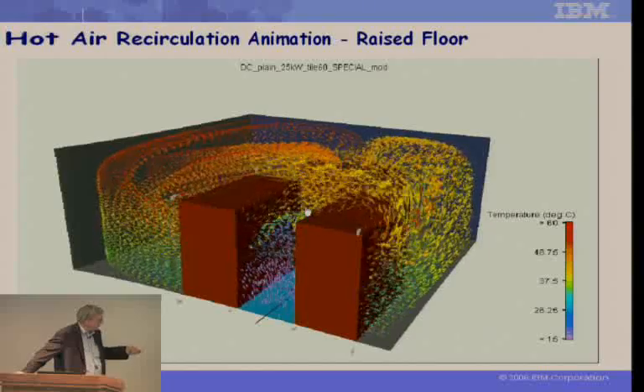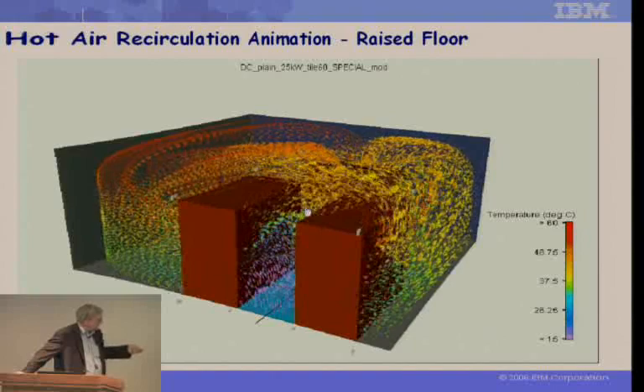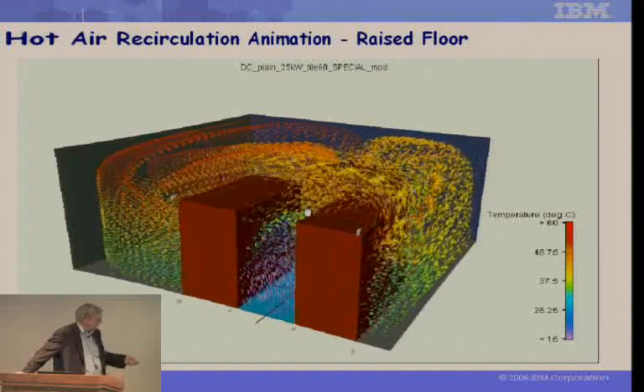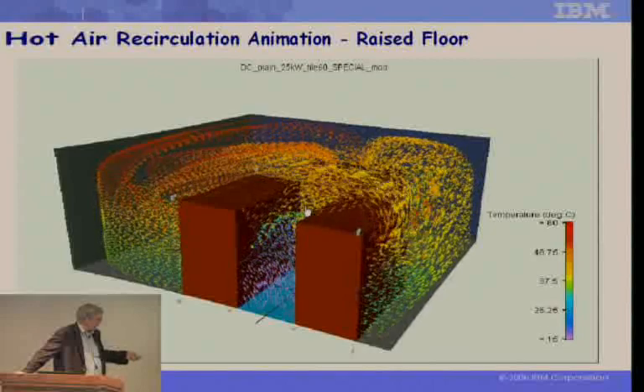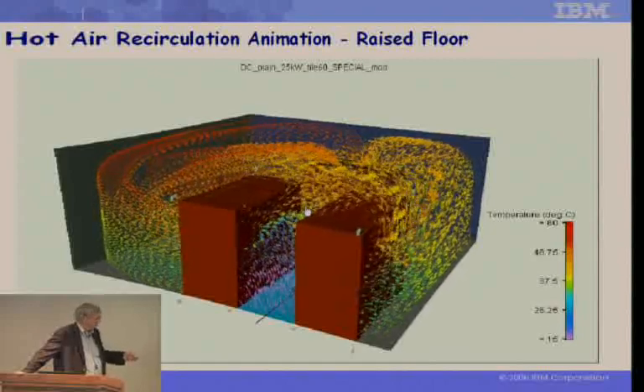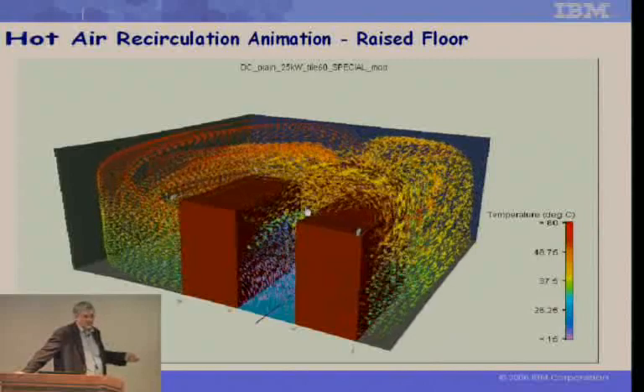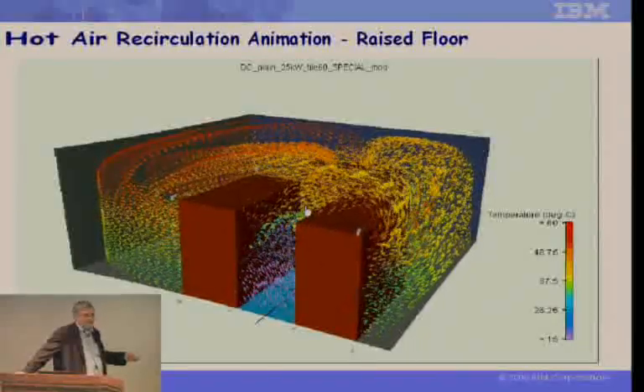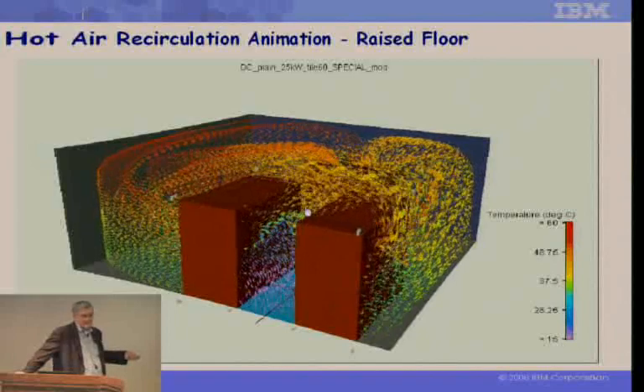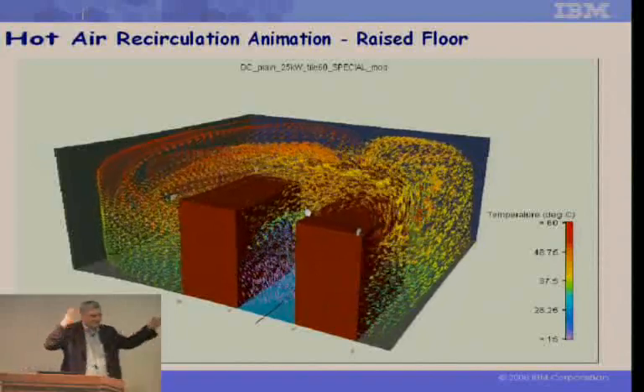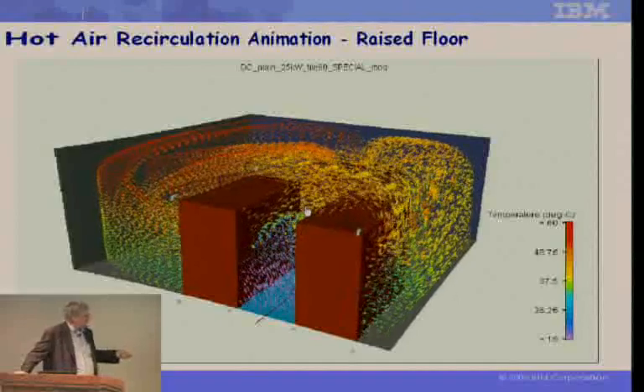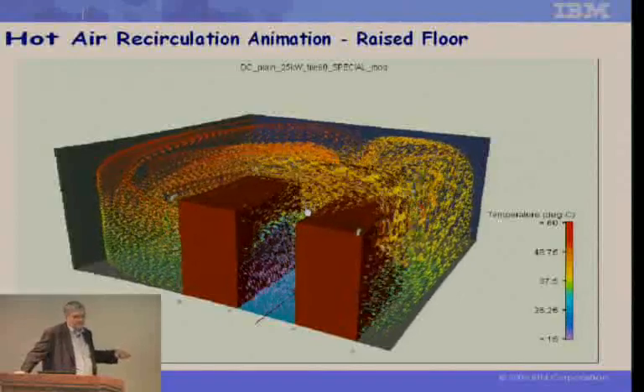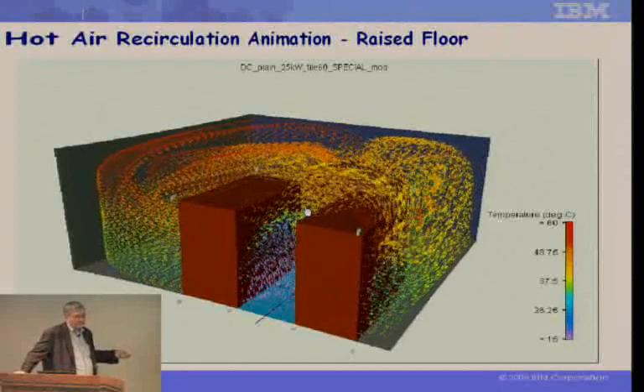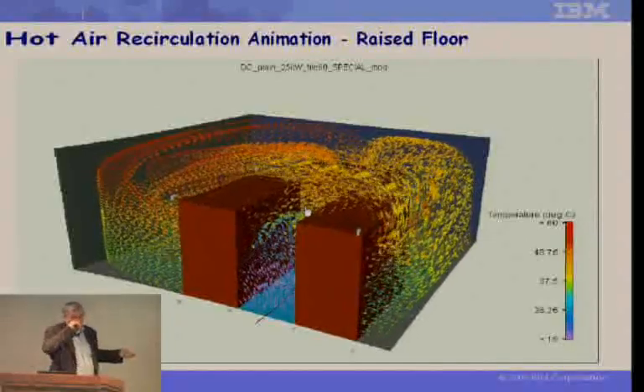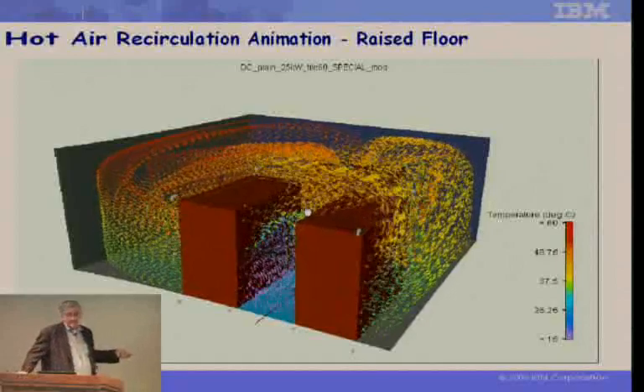Okay, these are 4 racks. The air conditioning unit is right back here. The cold air comes up from the bottom, goes into the machine, comes out the back, tries to get back to there. The concern is, with higher and higher powered machines, you cannot supply enough chilled air to these racks. It's just going to start pulling air from wherever it gets it. What happens is the hot air that comes out the back typically curls right over the top, and that hot air goes right into the front of the machine and can shut the machine down. That's a major concern in data centers.